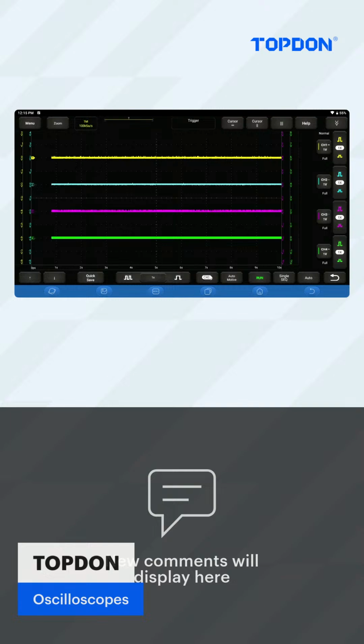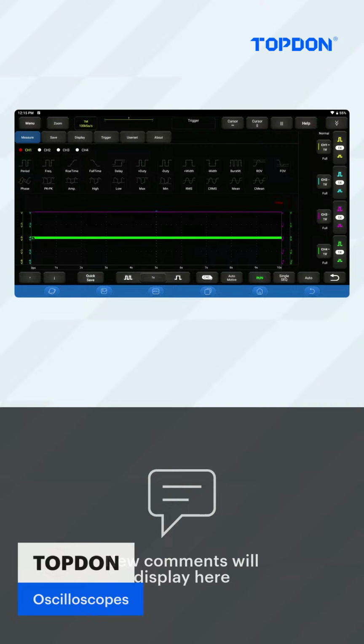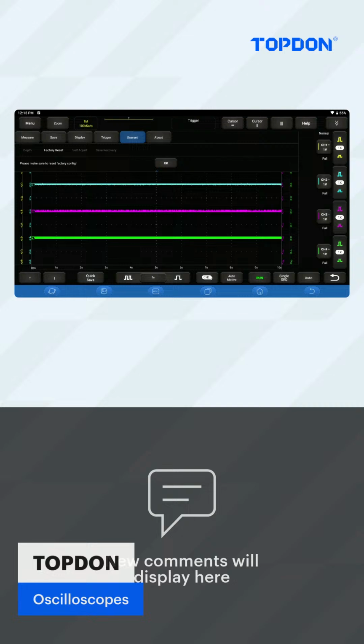So that factory reset button can be very helpful. Again, that's in Menu, User Set, Factory Reset. Now, the other one that's in this particular menu under Menu, User Set is Self Adjust. Now, the Self Adjust function is something you should perform on a semi-regular basis. If you're able, I'd recommend doing it at least once a day.